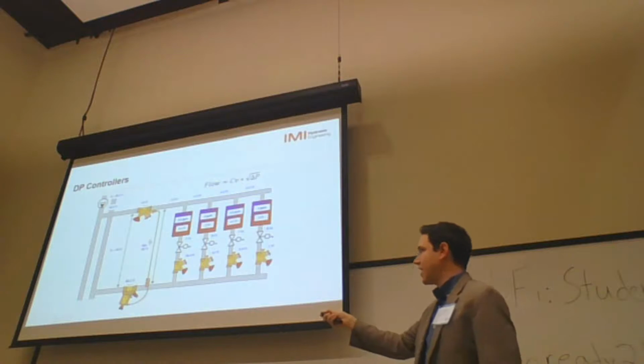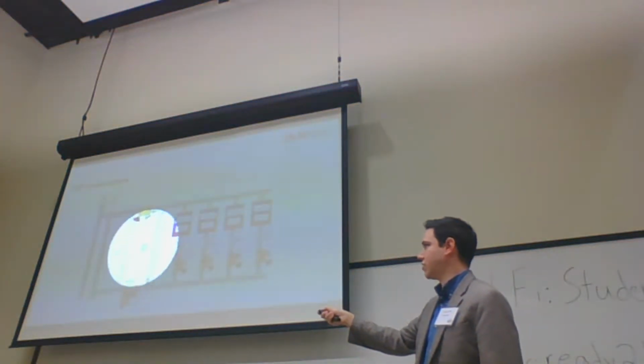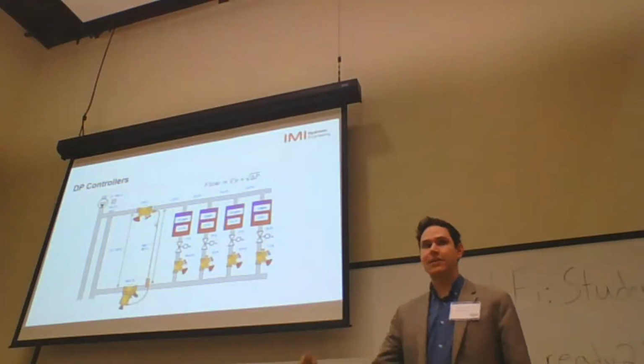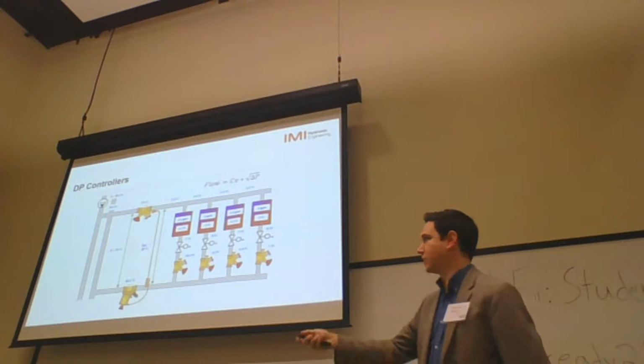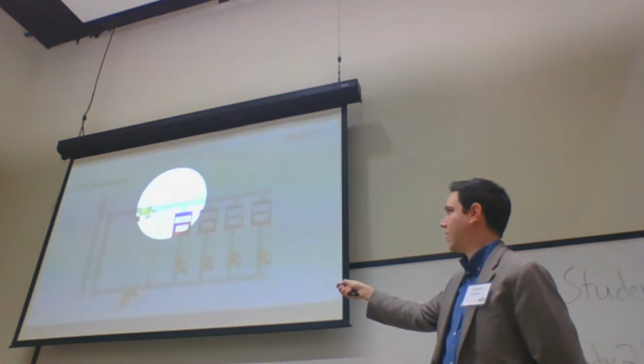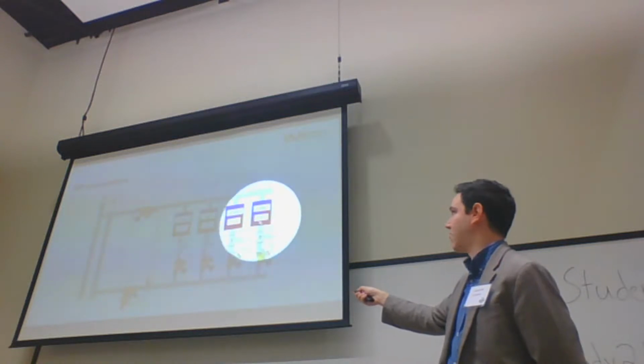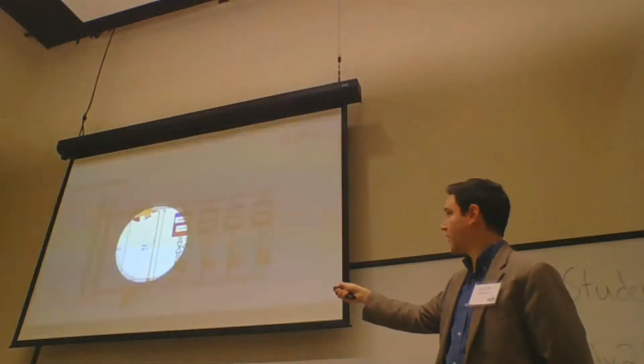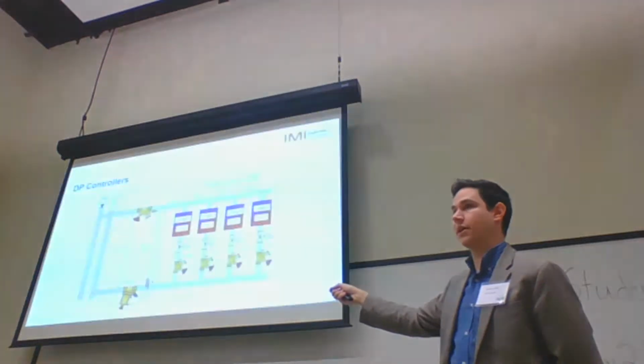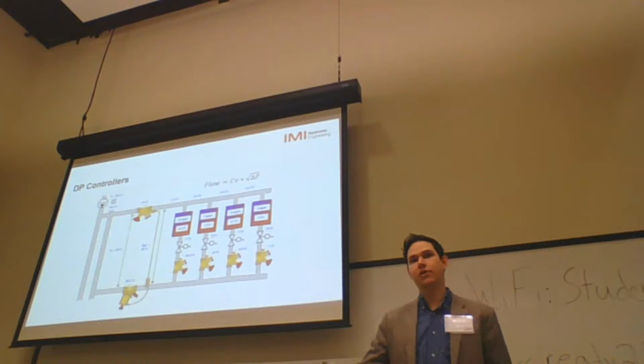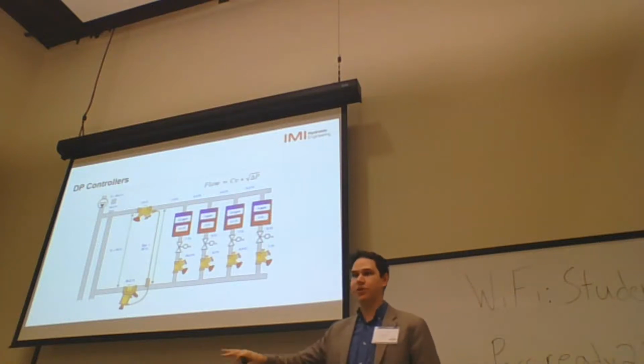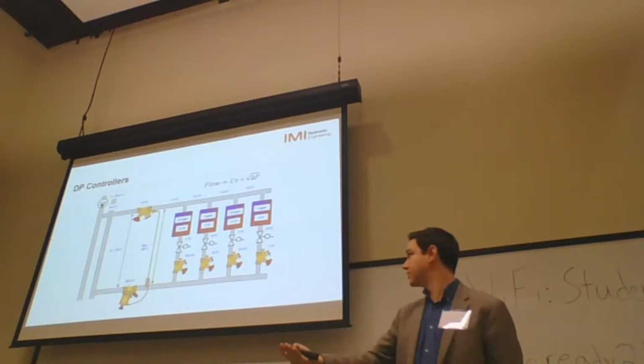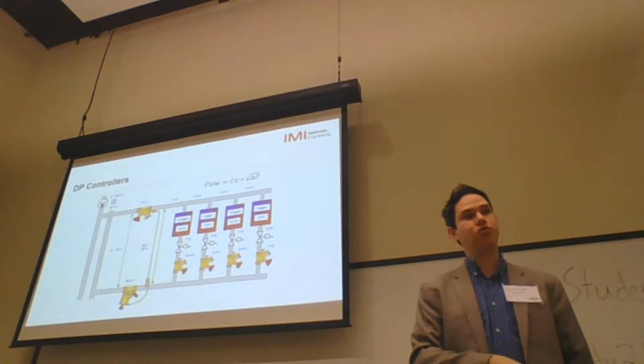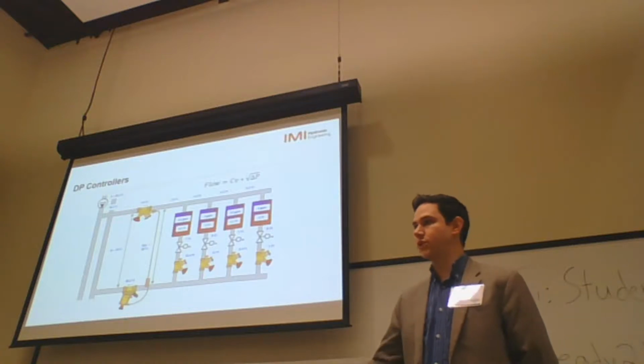If you're wondering where the 28 is coming from, like what is the differential pressure that I need to make stable on my branch? This is exactly the pressure drop that you need for your index circuit. So if you do simple math, 1.5 plus 4.5 plus 4.5 plus 6.5 plus 2 plus 8 plus 1, you get 28. Or with the same numbers, 1.5 plus 4.1 plus 7 plus 15.4, you get the same 28. So 28 is exactly the differential pressure that I need for that branch to work in the design conditions. It's exactly what we need. So you don't need more than 28 feet for this branch. So that's what the differential pressure controller is doing. It's keeping a stable differential pressure for that branch for exactly what you need.